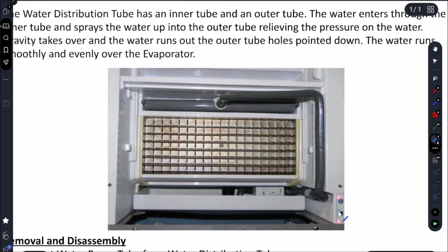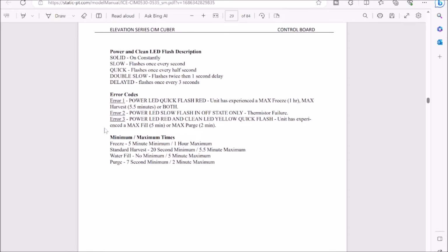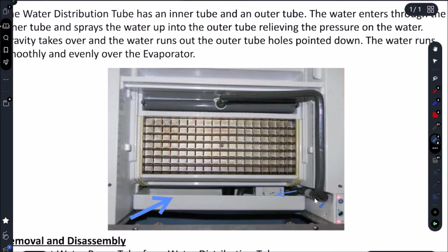All right, so let's quickly review what the freeze cycle is going to do. The first thing that's going to happen is the fill solenoid is going to fill our water trough right in here until our high level probe float switch closes. So how do we know the water trough is full? Well, if the water trough was not full, we would be getting error number 3, which is unit has experienced a max fill of 5 minutes, meaning in 5 minutes we have not filled up this water trough. And once we have water, our compressor is going to start up, our refrigeration cycle is going to start. So we're going to pull water from the trough here, bring it up through this water manifold, and it's going to distribute right through here onto this evaporator coil.